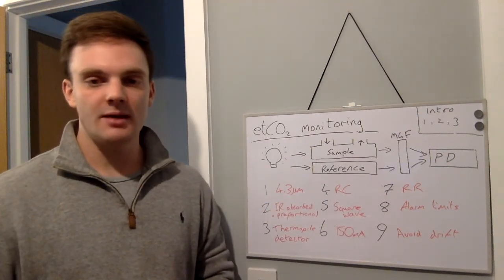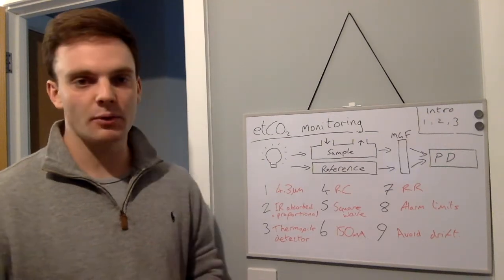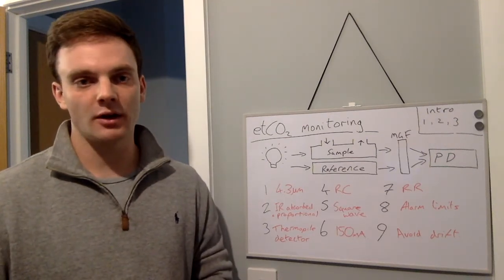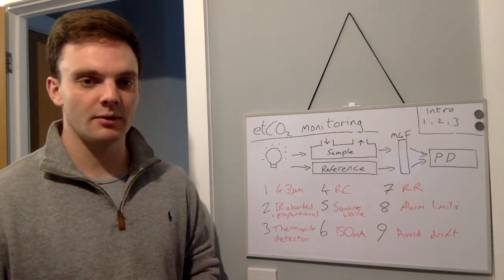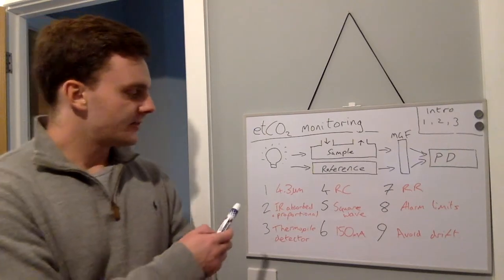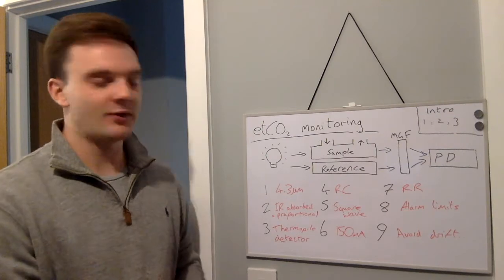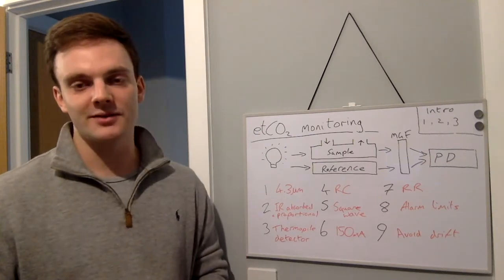For me, I've gone through the process at nine points in order to try and include everything that's important with end tidal CO2 analysers. So the first point: CO2 molecules absorb infrared light at a wavelength of 4.3 micrometres.